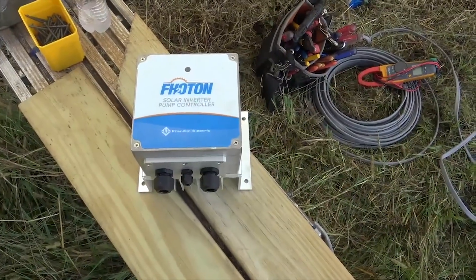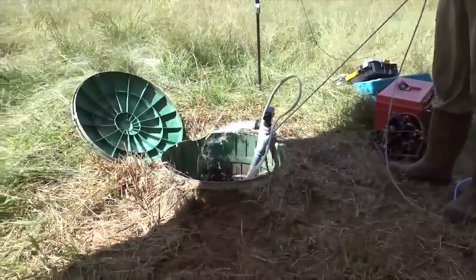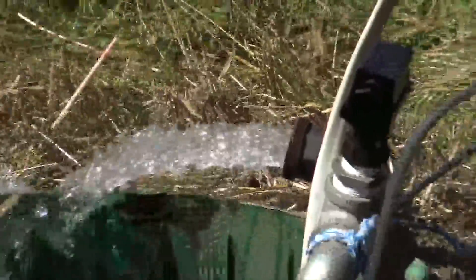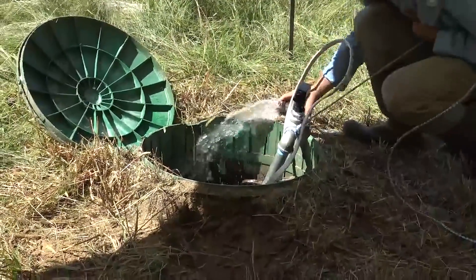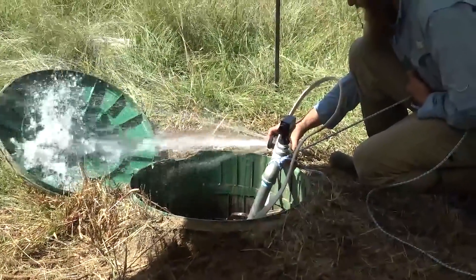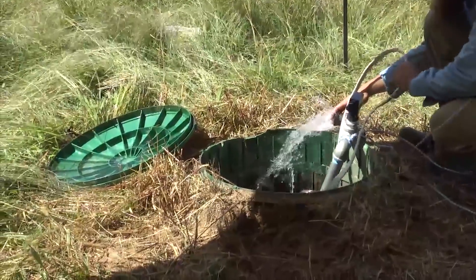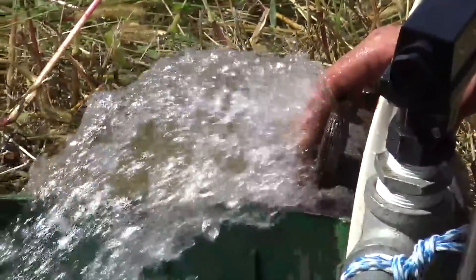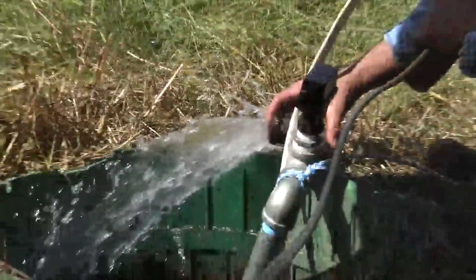We're looking at 30 to 32 gallons a minute as our goal. We've made connections with the Fhoton controller and we're doing a test — that's an inch-and-a-quarter pipe blasting away. We bypassed the flow sensor just to prove we are pumping water. Now it's going through the flow sensor and moving a lot of water. We could do a bucket check to figure out exact gallons per minute, but we're happy.